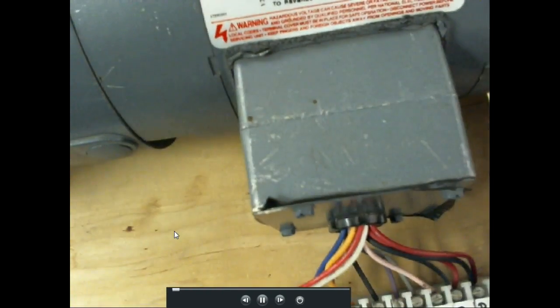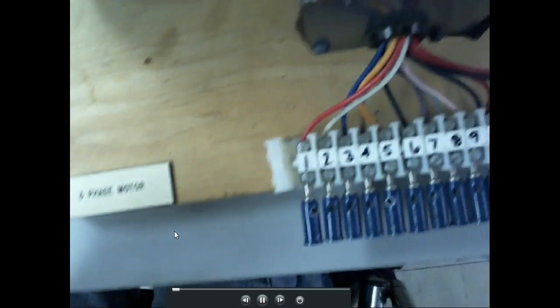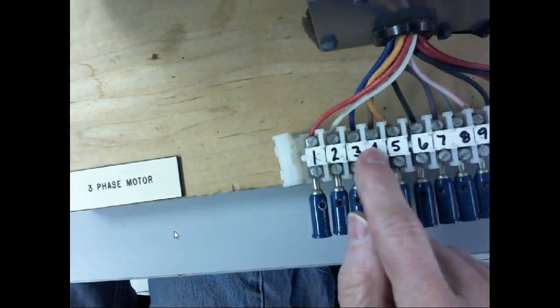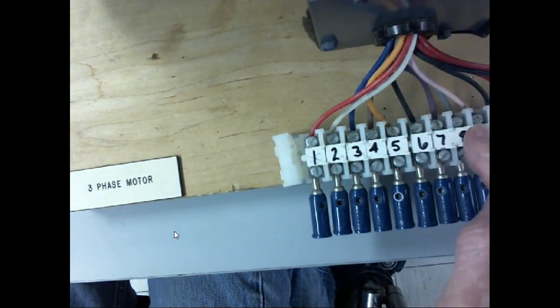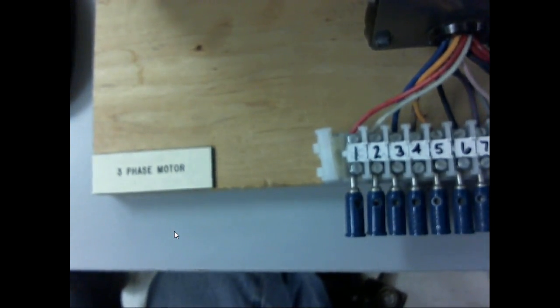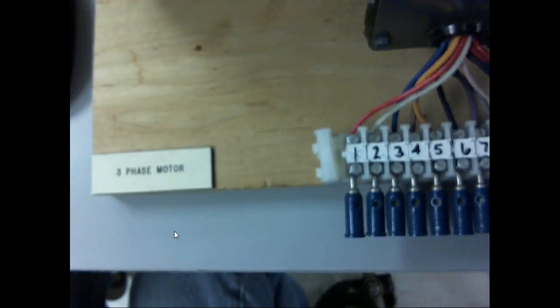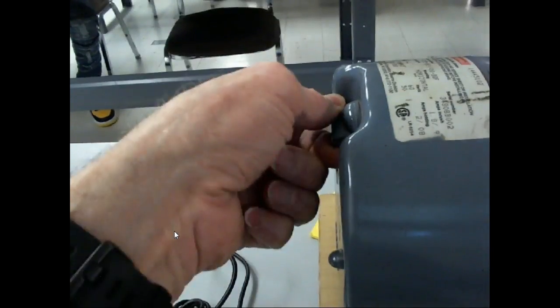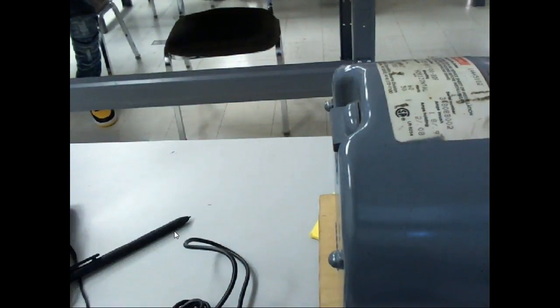So what it says is, when I look at my terminals, here's our terminals: 1, 2, 3, 4, 5, 6, 7, 8, 9. This is brake. What I want you to do before you use this thing is attempt to spin the shaft with your hand. If you can't spin it, don't put power on this thing. The manual control of the brake is back here on the back, and you should be able to turn it, and it should lock down, and now the motor should spin freely.